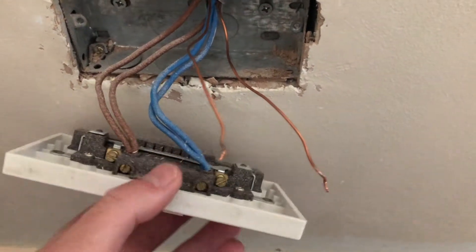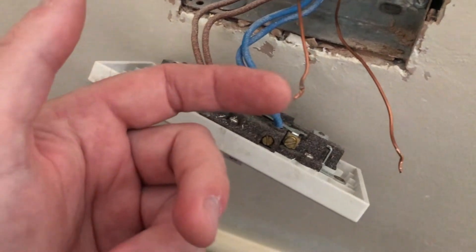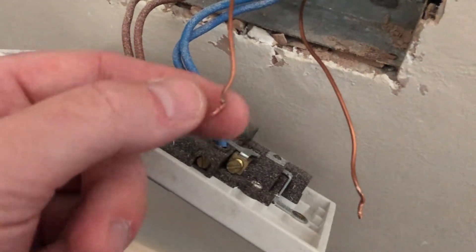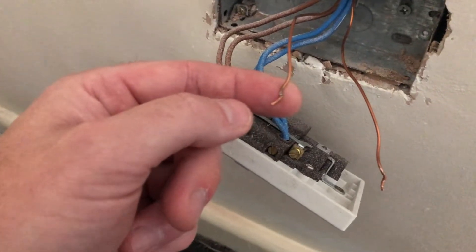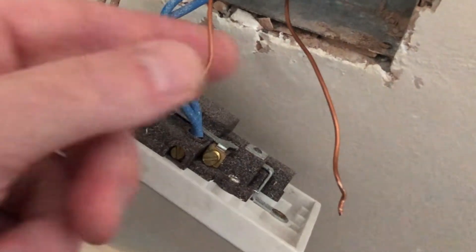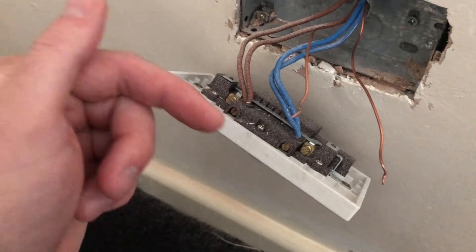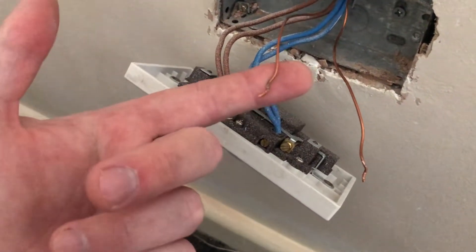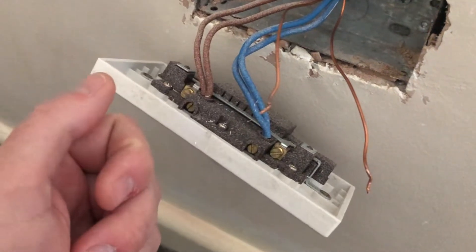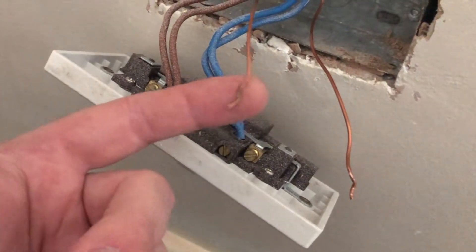One of the problems we face with traditional sockets — I've just disconnected these so you can see — is that the conductors get slightly crushed when they go inside the terminations. If you under-tighten they pop out; if you over-tighten you squash them and they can become brittle. I'm going to wire this new socket up, then disconnect the conductors and let you have a look at the damage the new socket causes — which should be minimal.